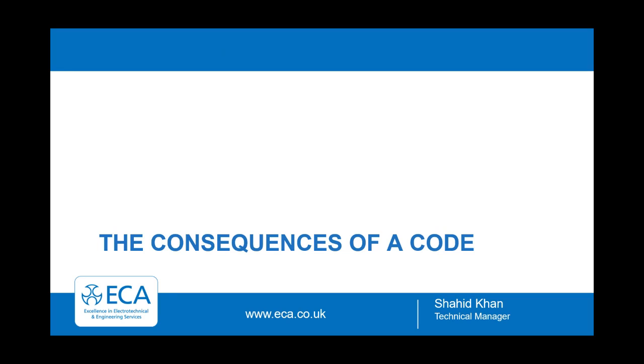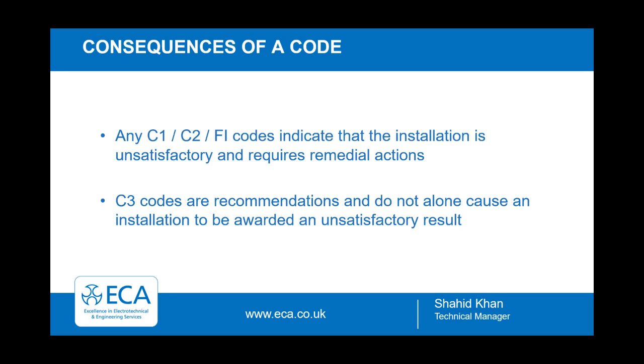The consequences of awarding a code. Any C1, C2 or FI codes awarded on an EICR deem that the installation contains dangerous elements, thus is unsatisfactory. Whereas awarding a C3 code alone does not necessarily mean that the installation is unsatisfactory. It doesn't mean it's unsafe.